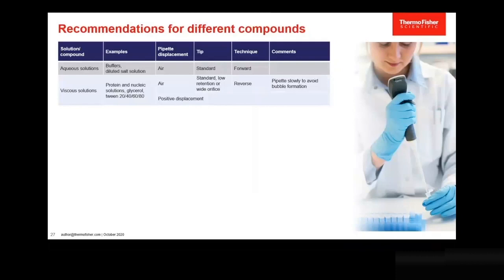For more viscous solutions — protein and nucleic acid solutions, glycerol at 20, 40, 60, 80 percent, etc. — there is a choice of pipettes you could use. You can use an air displacement pipette with standard, low retention, or wide orifice tips, whichever gives the best result, and consider using the reverse pipetting technique. Pipette slowly to avoid bubble formation. Or you could consider using a positive displacement pipette with standard tips.